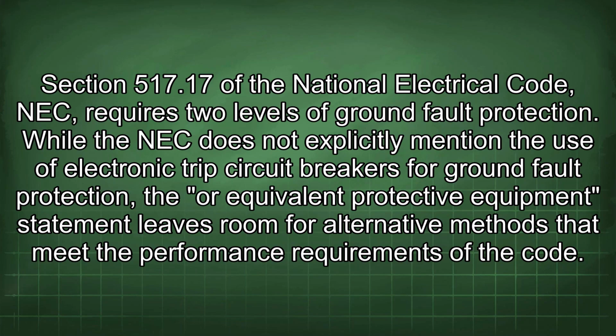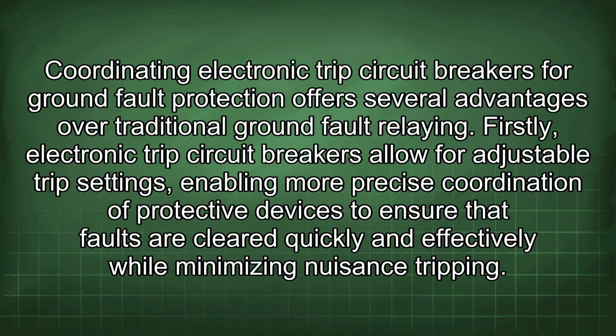517.17 of the National Electrical Code (NEC) requires 2 levels of ground fault protection. While the NEC does not explicitly mention the use of electronic trip circuit breakers for ground fault protection, the "or equivalent protective equipment" statement leaves room for alternative methods that meet the performance requirements of the code. Coordinating electronic trip circuit breakers for ground fault protection offers several advantages over traditional ground fault relaying.